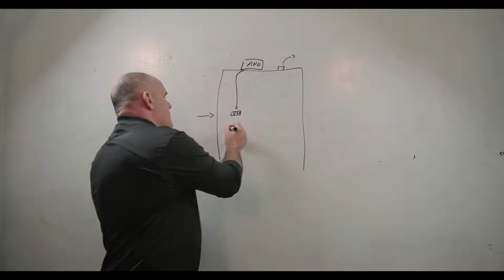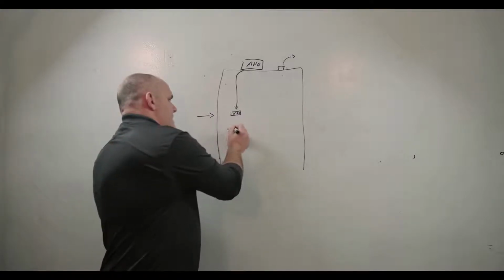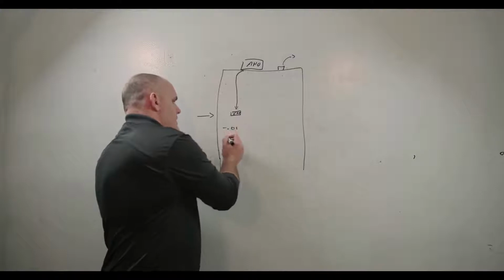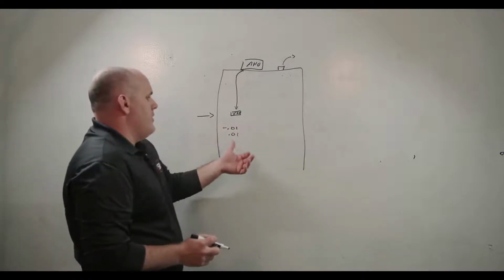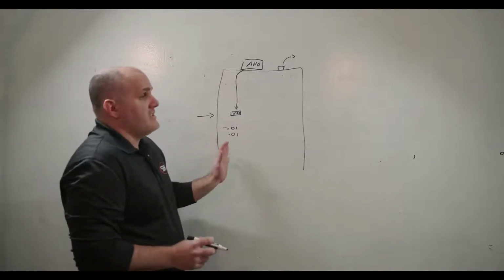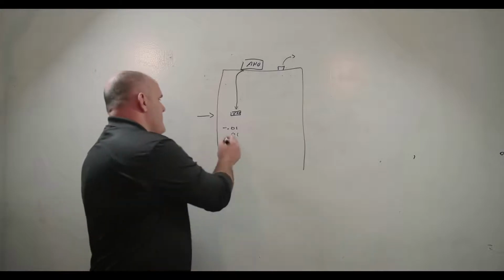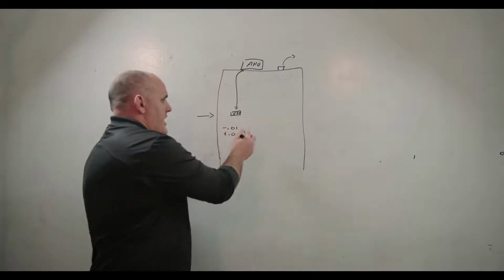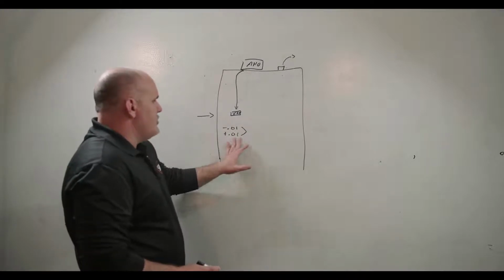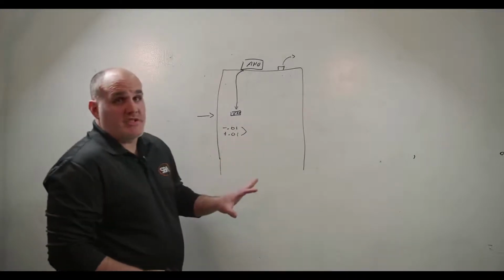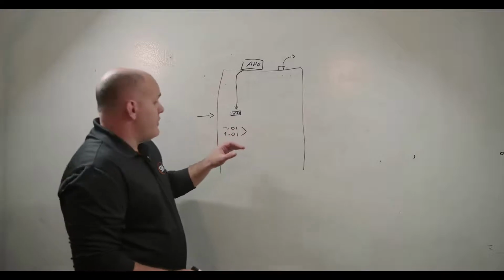That being said, so that's building static, right? And with building static, we're aiming for anywhere from negative 0.01 to a positive 0.01. These are extremes, right? Anything in between this.